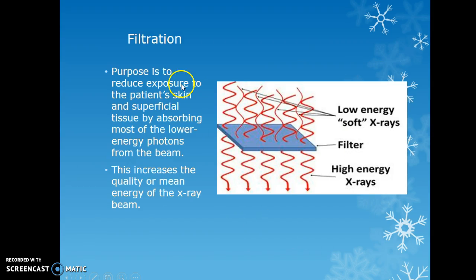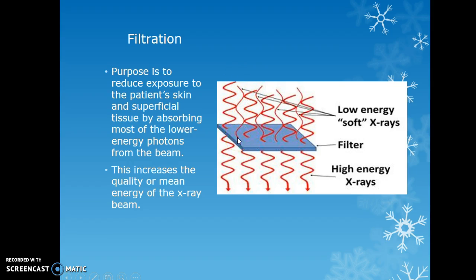The basic purpose of filtration is to reduce exposure to the patient's skin and superficial tissue by absorbing most of the lower energy photons from the beam. These soft, low-energy, long-wavelength x-rays are filtered out before reaching the patient, as they aren't sufficient to penetrate through to the image receptor anyway. This increases the quality or mean energy of the x-ray beam.